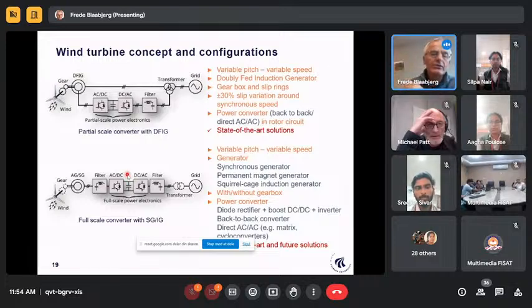The alternate solution is the full-scale converter, where we control the power fully of the generator, doing AC to DC, and then interface to the grid doing DC to AC. This gives full controllability, and maybe also a wider variable speed range. What is also coming out of it is the ability to decouple the two systems. So if something happens at the grid, we can decouple it from the generator, and also opposite. However, the challenge in general with this technology is we have to convert the power twice, while we don't have to do it up here.